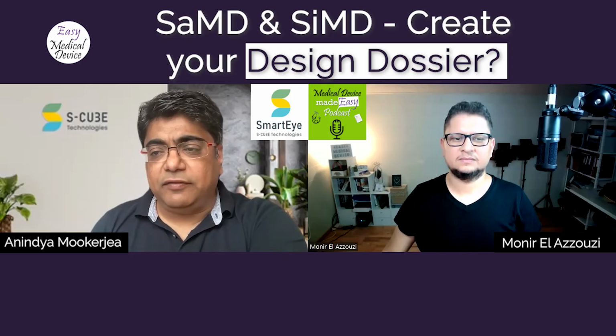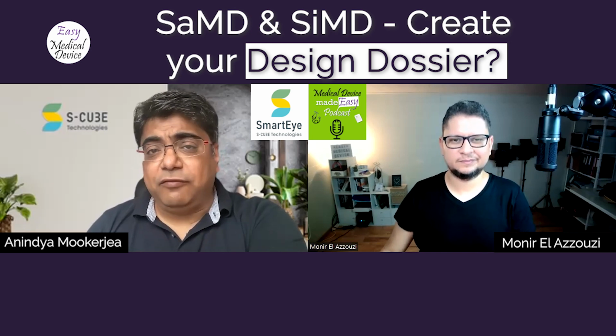Sure. To ensure that you are designing and developing the software in the right way, it's very important that you set up a good platform and have the right framework. Thankfully, for medical devices, we have a harmonized standard, which is ISO 13485. It is not specific for software, however it gives you a very good set of processes, procedures, templates.